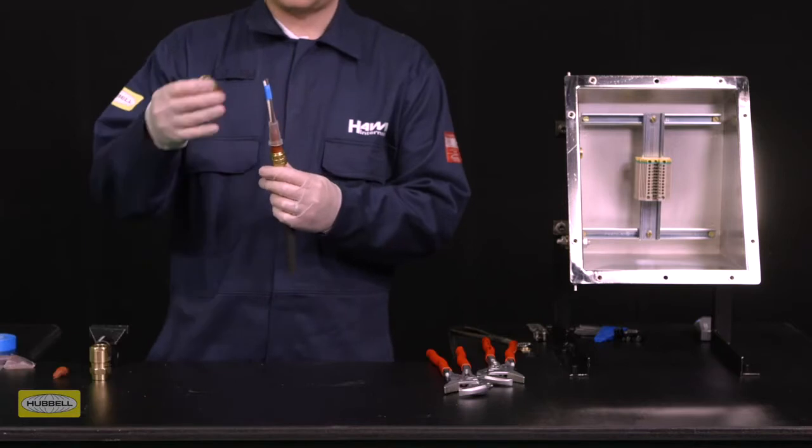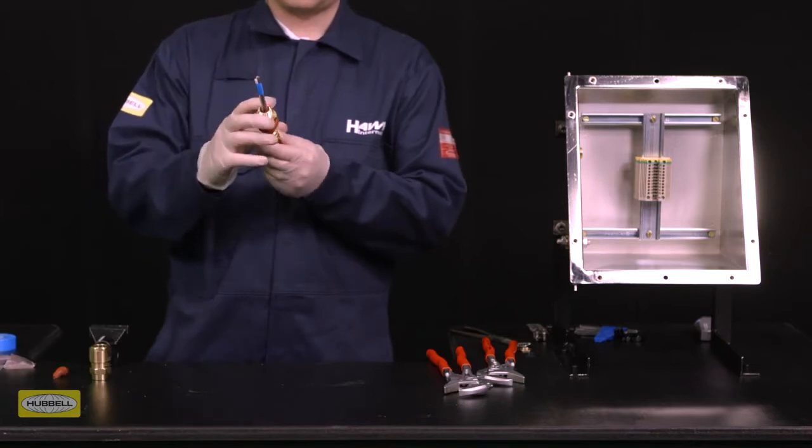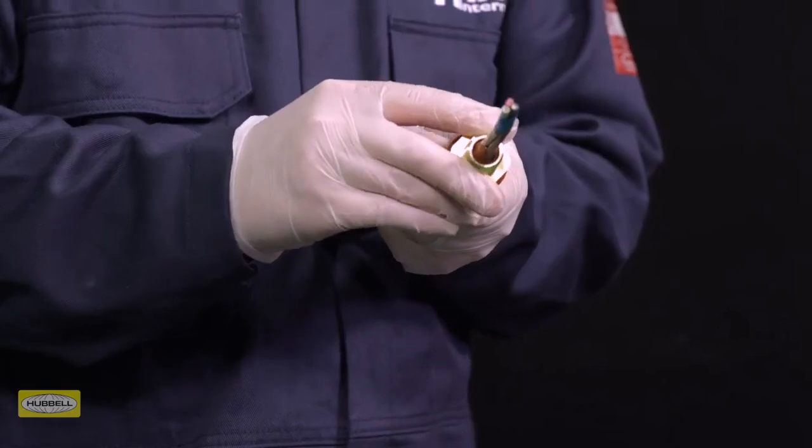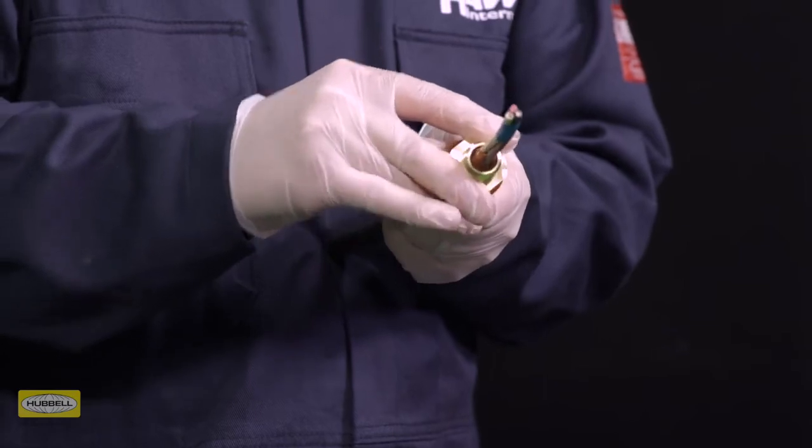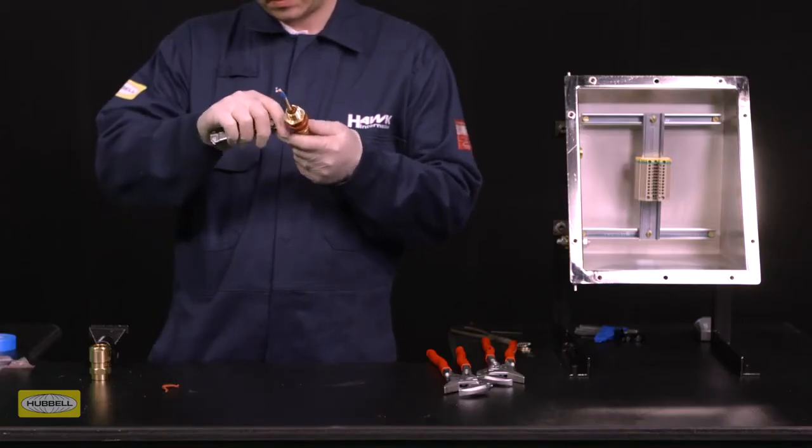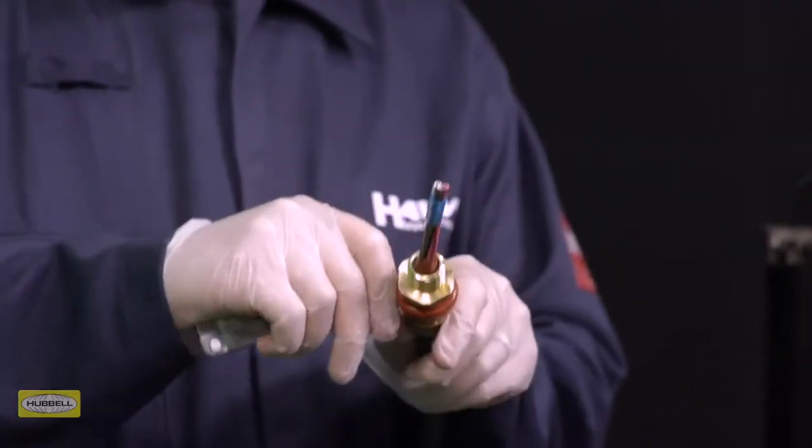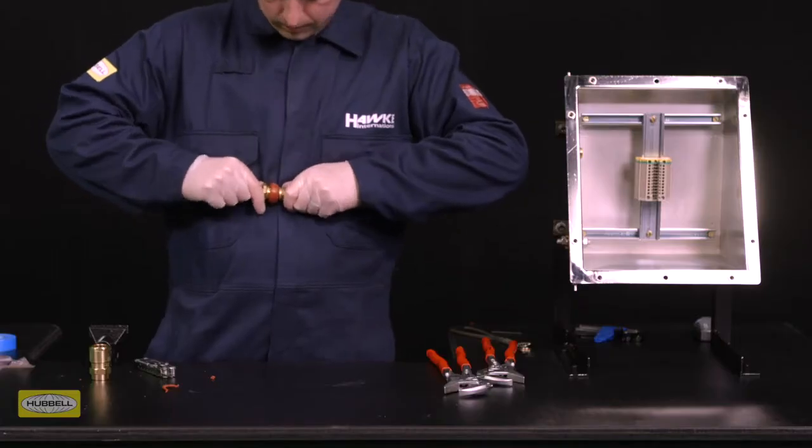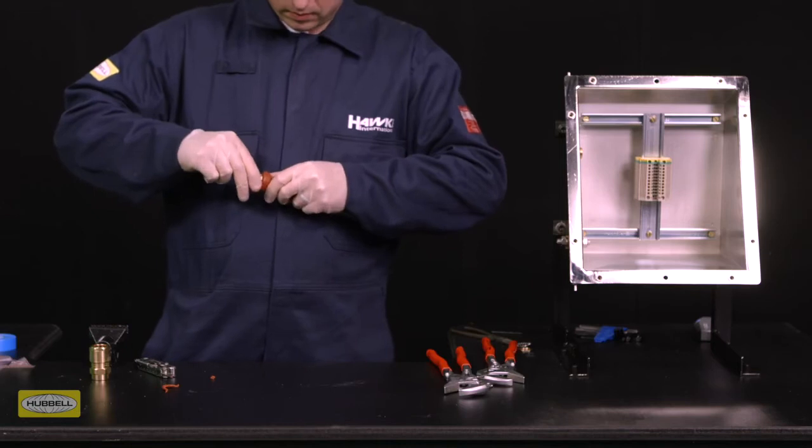Fit the entry pot and press down to push the compound chamber towards the armour clamping spigot. Remove any surplus compound, particularly where the compound pot meets the spigot, and continue to press down until the compound pot sits correctly on the spigot component.